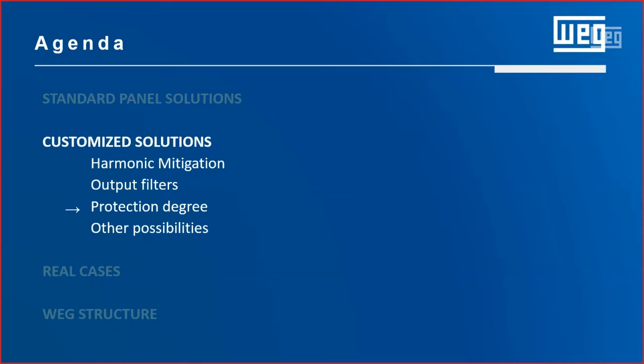So now let's talk a little bit about protection degree. A variety of different environment types can be found in industry, and each one requires that all equipment operating in such environments be suitable and reliable to withstand such harsh conditions. The wrong choice of the protection degree can cause damage to the drive electrical parts due to contaminant access to some sensitive parts. These applications require an enclosure with proper protection degree to withstand the ambient conditions.